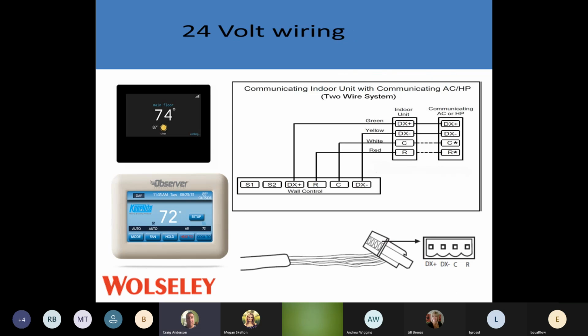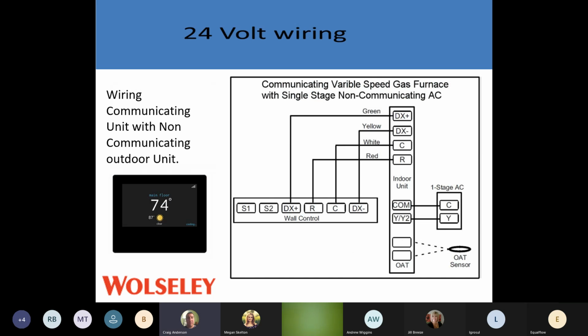Typical 24 volt wiring for a communicating stat: 4 wires upstairs, 4 wires to the indoor unit, whether it's an Ion or an Observer stat. We have a communicating indoor unit and a communicating stat. The customer has a standard AC outside. We can hook it up. We just need to tell that communicating stat we have an AC on it.